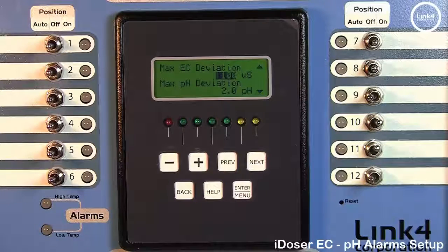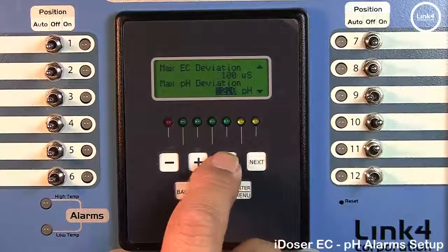Now deviation is if you have a backup sensor and there is a separation from the main sensor value and the backup sensor value. What will happen is it will throw an alarm and will stop dosing. Now, deviation checks for the separation of values between the EC and pH values only, not temperature. And these fields can be adjusted by simply hitting next and previous to highlight the fields and hitting plus and minus to change the numerical values. Once you have set this, hit next.